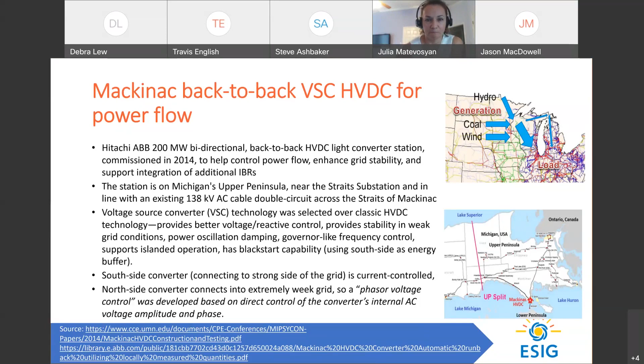As I mentioned, the north side converter connects to an extremely weak part of the grid. I took this phrase from the article that describes this project: phasor voltage control was developed based on direct control of the converter's internal AC voltage amplitude and phase. If you read this definition, that's actually what goes into the definition of a grid forming inverter, and that's why I picked this project to have in this set of grid forming inverter surveys. So it does act as a grid forming inverter in this application. Next slide, please.